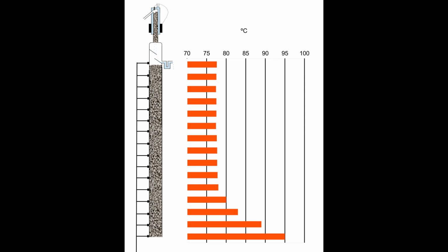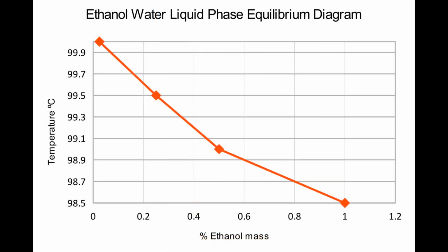When operating as a continuous still, there is an alternative temperature-based control method which uses the bottom temperature as the sole control parameter, rather than relying on a festoon of sensors up the column. With continuous distillation, the still gets a split between the product and bottom's ABV. If you increase the steam flow, the alcohol content of the bottoms will fall and its temperature will rise. Conversely, if you reduce the steam flow, the alcohol content of the bottoms will rise and its temperature fall.